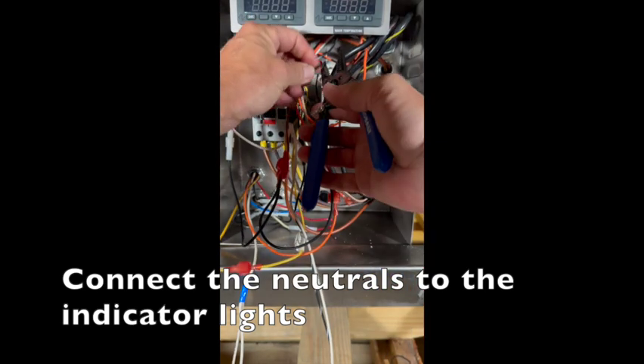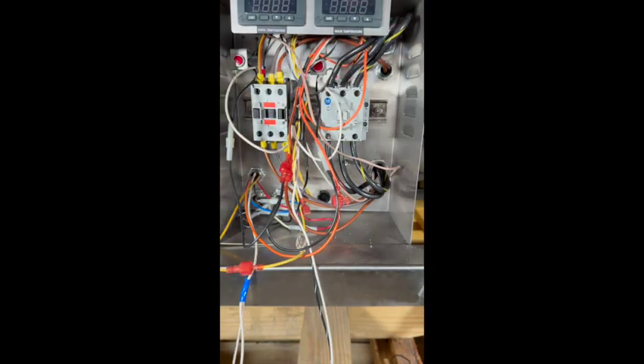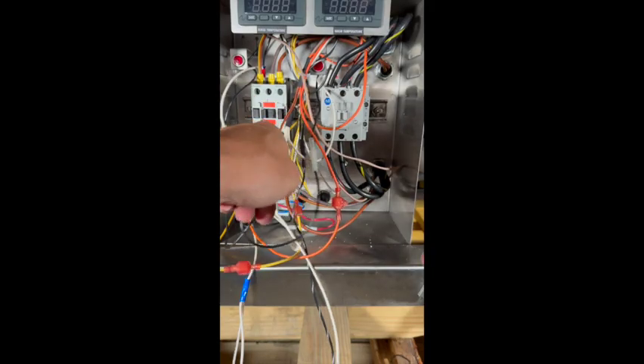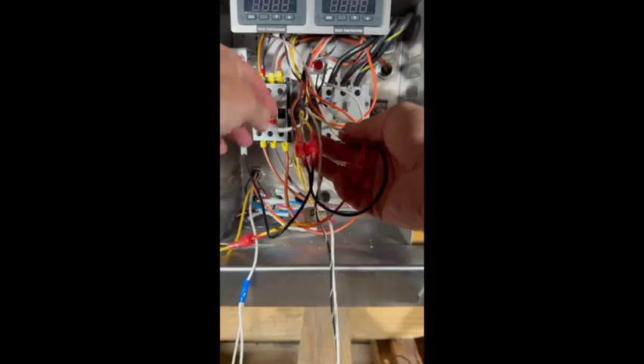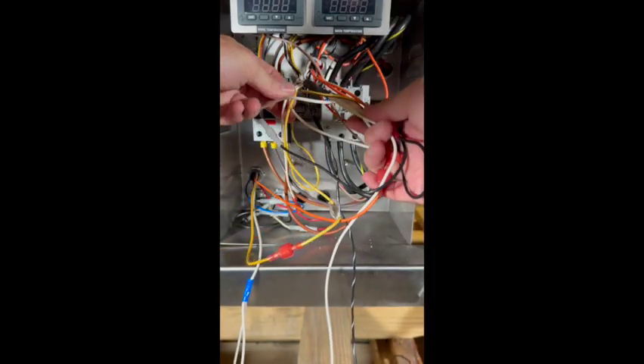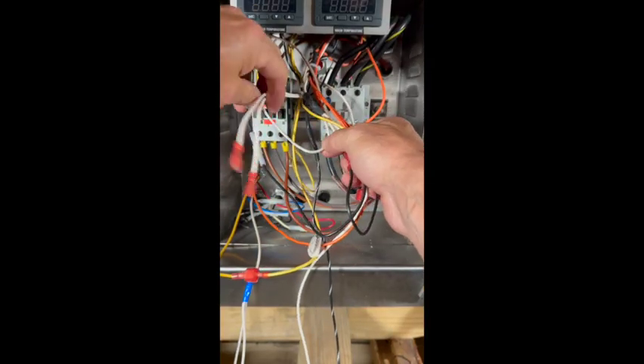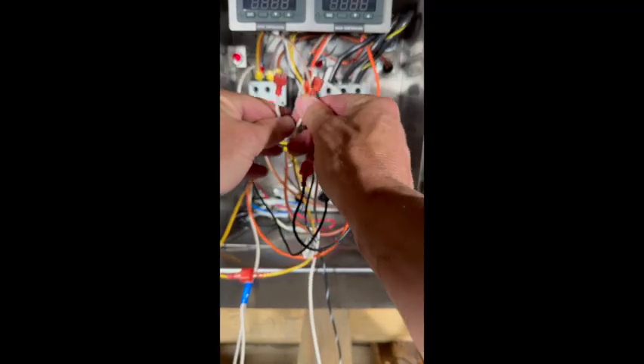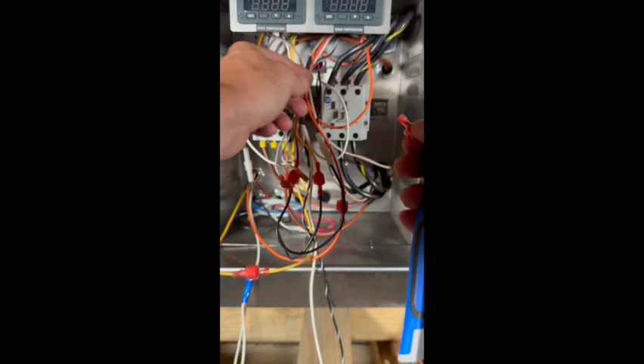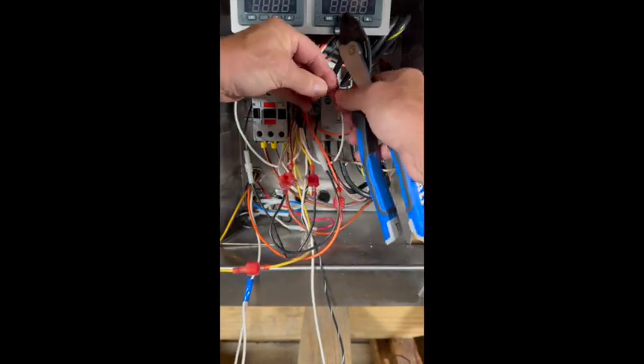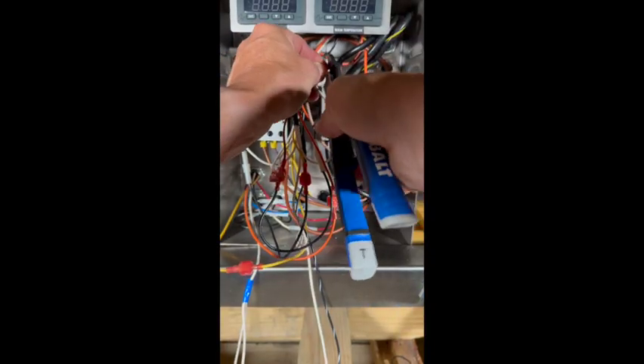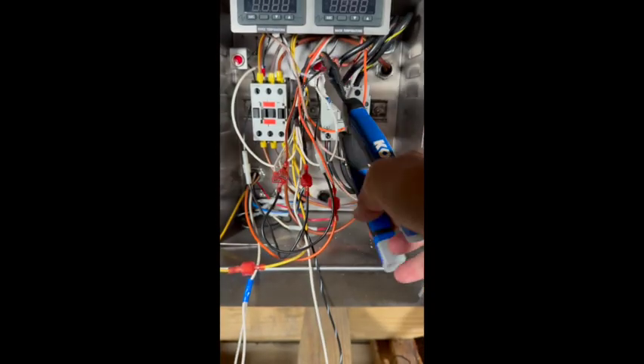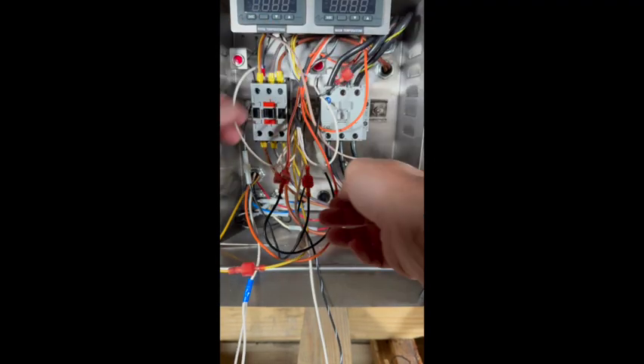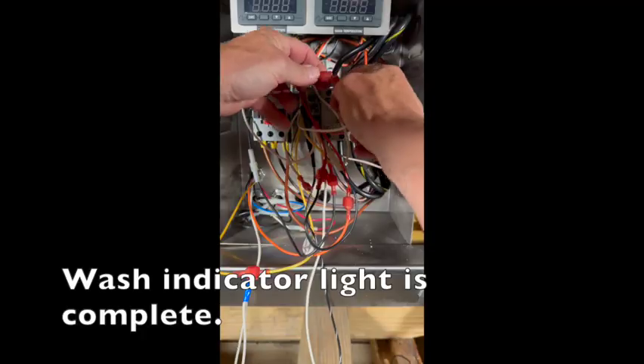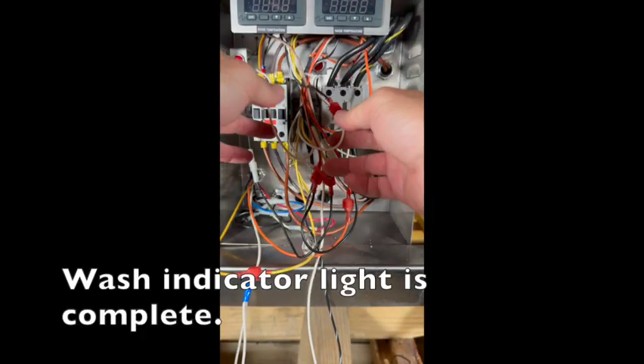Now we do need to take care of the neutral side of those indicator lights. So on the indicator lights themselves, they're probably going to have some type of terminals attached to the factory supplied black wires. So we're going to remove those terminals. We're going to look through our wiring harness here, and we're going to look for the remaining white wires. There should be 2 left white wires with female terminals on them. So we're going to get a male terminal, and we're going to connect it to that remaining wire that's on the indicator light. So now you can just take one of those neutrals and connect it back to the light.